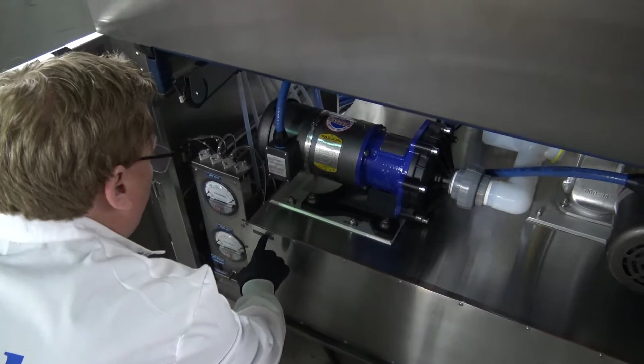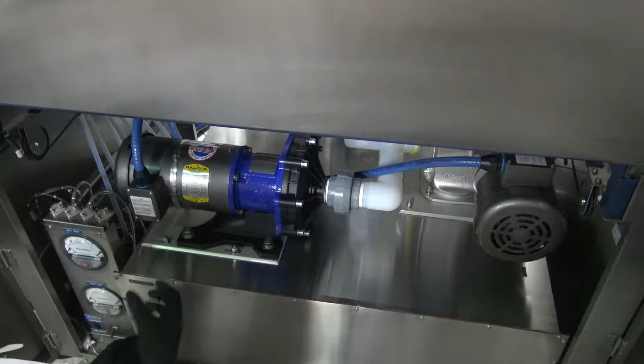So there's the bottom chamber. We have a note here: replace the HEPA on 10/9/2018. This has a brand new HEPA filter, part of the order. It's inside of this module, so we can't take it out for the demo. We rebuilt the motor. The motor becomes one of the failure points on the tool. The reason is customers tend to not clean everything off their cassettes. They might leave labels and stuff on there, and as they get washed off, they sometimes get stuck in the pump mechanism, or sometimes what happens is those little white ball bearings, if you start getting old spindles, the ball bearings fall out and they get stuck inside the pump.